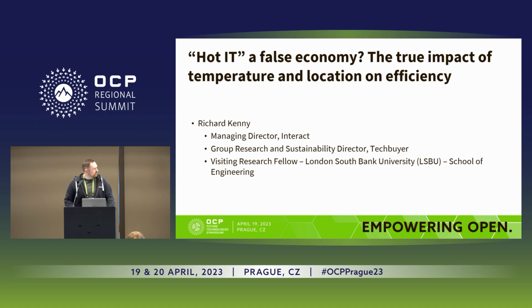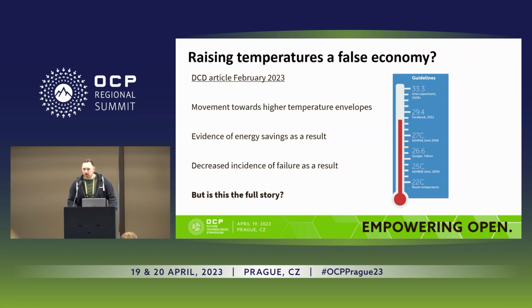So I don't know if you're aware of this at the moment, but Equinix is looking at making a default 27-degree shift. That's the top of what we would class as an ASHRAE allowable envelope. The idea was that it will save carbon, it will save energy. That's not necessarily true, and so I'm going to break down why that might not be true.